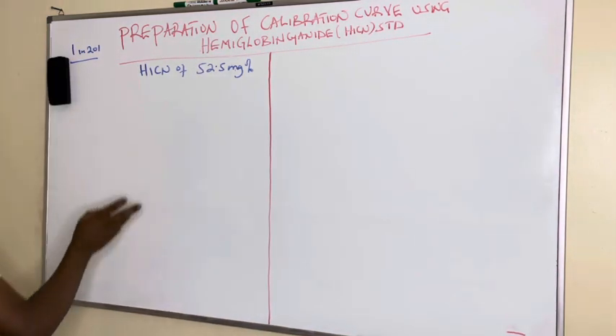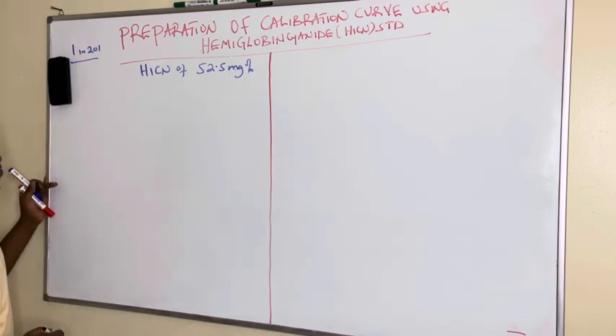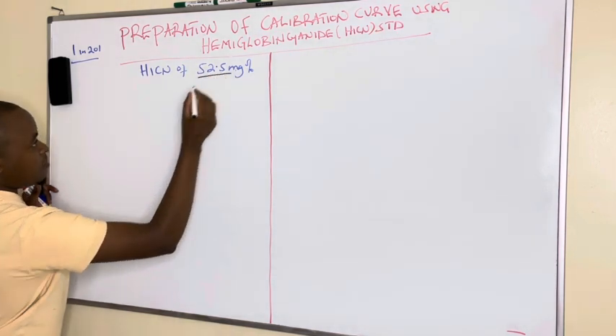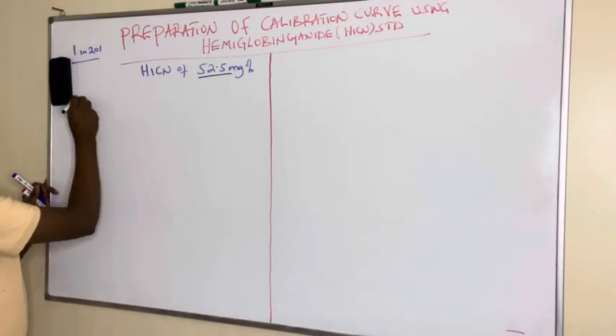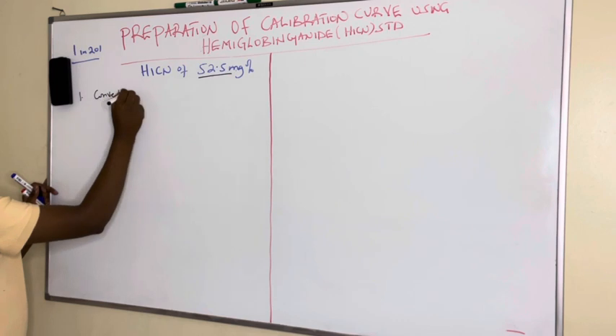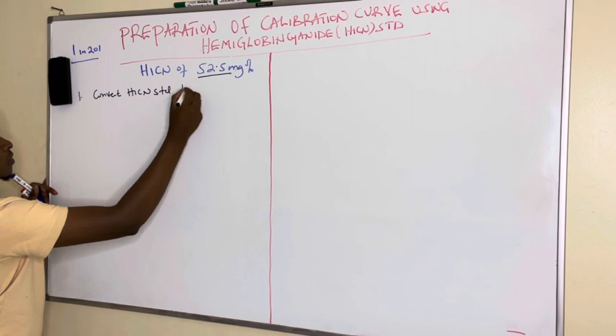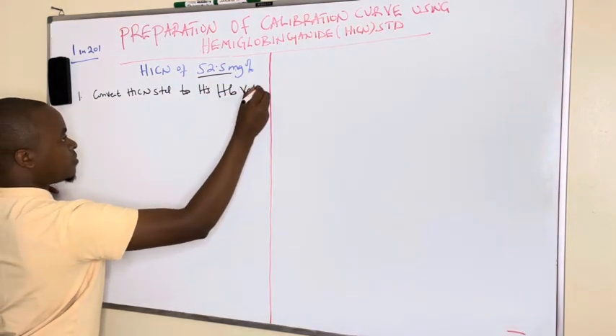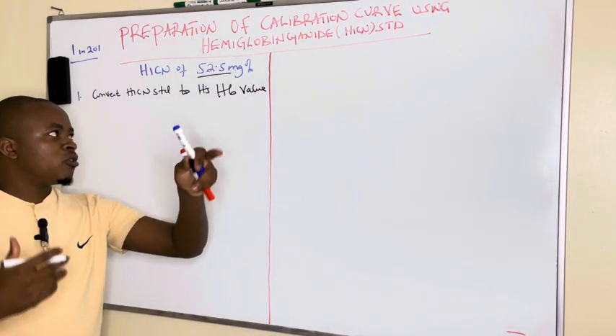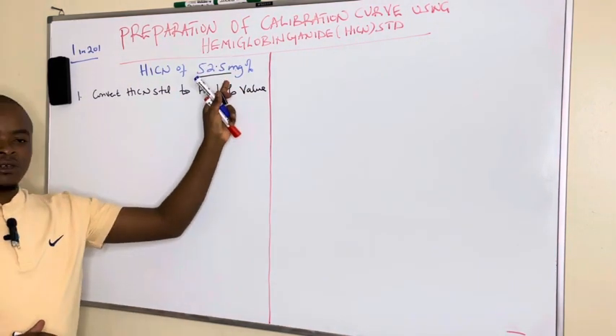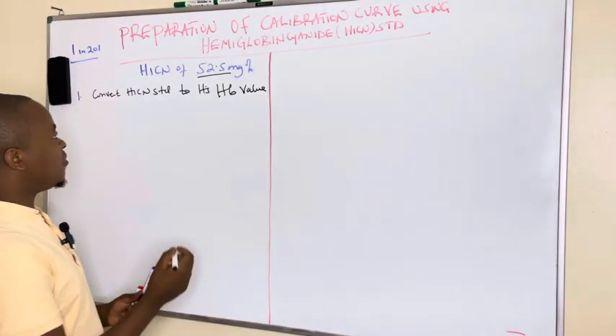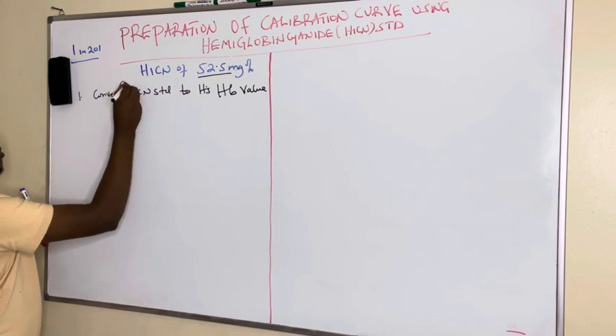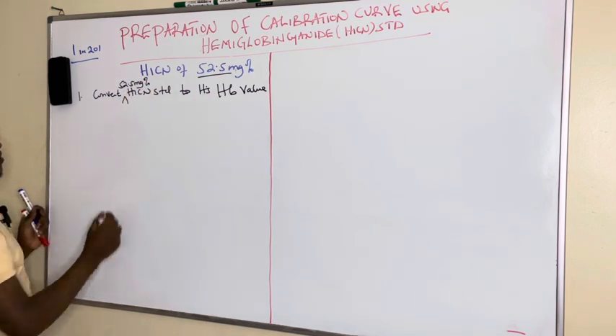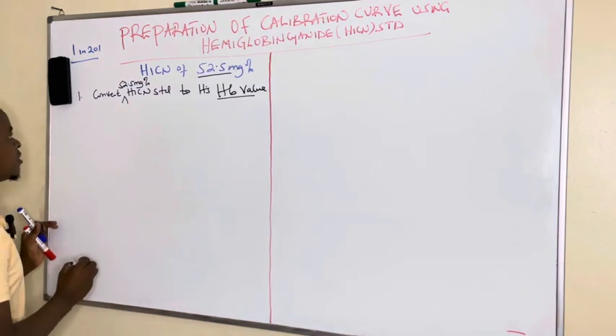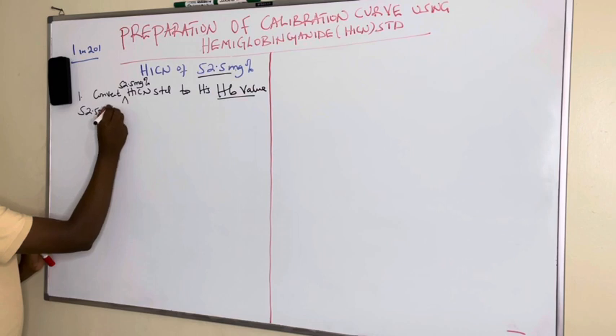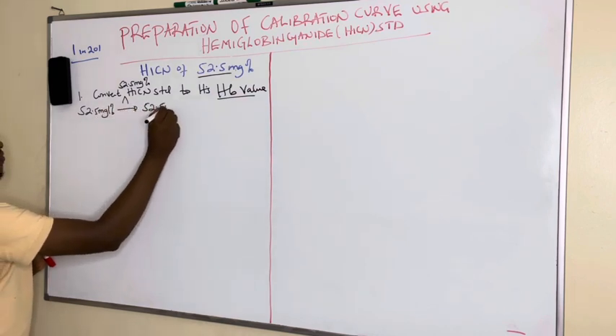So the first procedure we do in this type of calibration curve preparation is to convert this cyanide hemoglobin standard to its original HB value. The first step is to convert the HiCN standard to its hemoglobin value. Because, as I told you, to get this standard the preparer used a known hemoglobin, we have to take it back. So we are converting 52.5 milligrams percent of HiCN standard to the HB value. What we do is that 52.5 milligrams percent means 52.5 milligrams per deciliter.